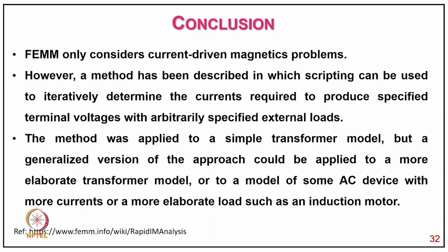Now coming to the conclusion. FEMM only considers the current driven magnetic problem. However, a method has been described in which the script can be used to iteratively determine the current required to produce a specified terminal voltage with an arbitrary specified external load. The method was applied to a simple transformer model, but a generalized version of the approach could be applied to a more elaborate transformer model or to a model of some AC device with more current or a more elaborate load, such as an induction motor.